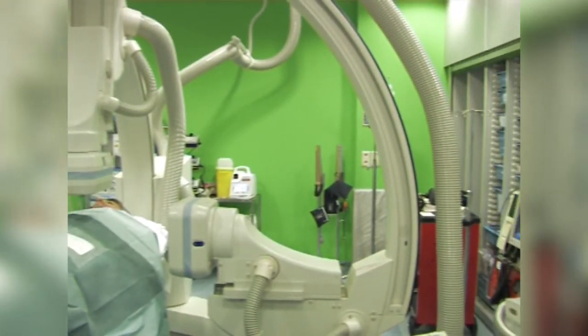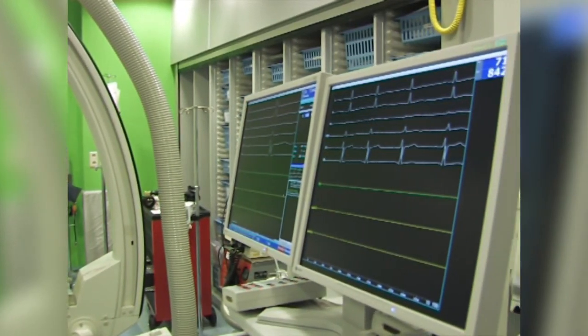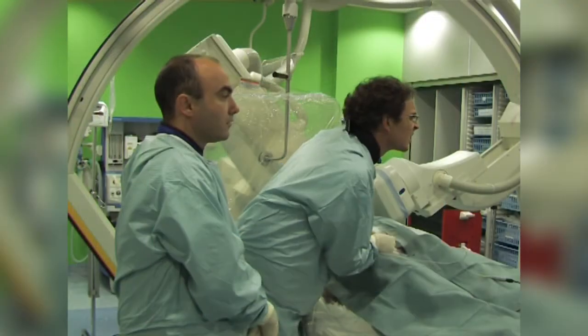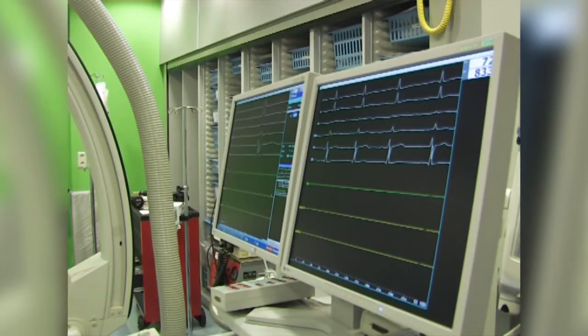All models have a built-in two-channel cardiac stimulator. The benefits of a built-in stimulator are easy to figure out, because we have one single device instead of having two — a recorder and a stimulator — making it more space-efficient and user-friendly. The EP Tracer 38 has 20 intracardiac channels, the EP Tracer 70 has 52, and the EP Tracer 102 has 84 intracardiac channels.